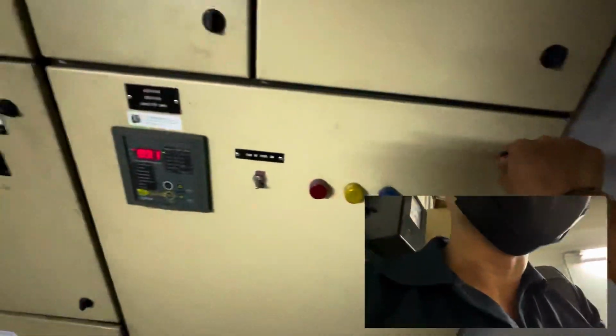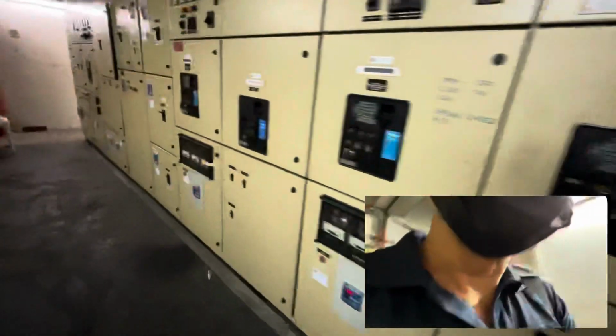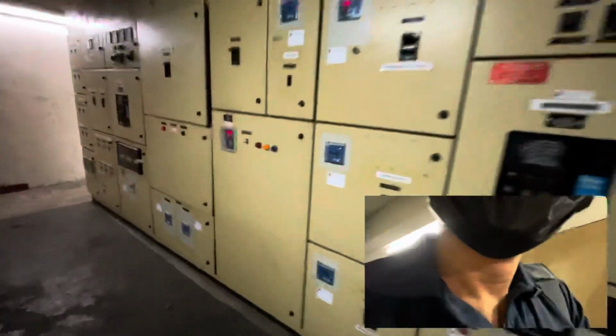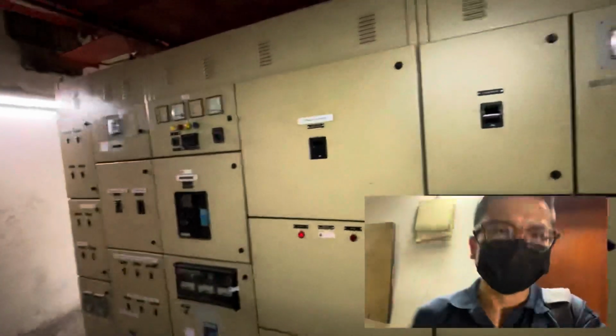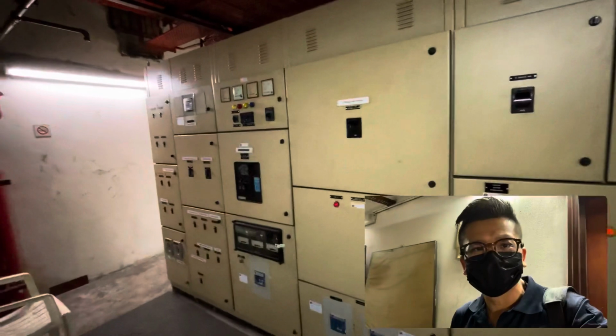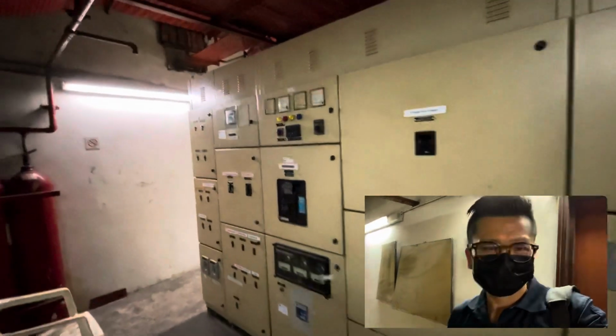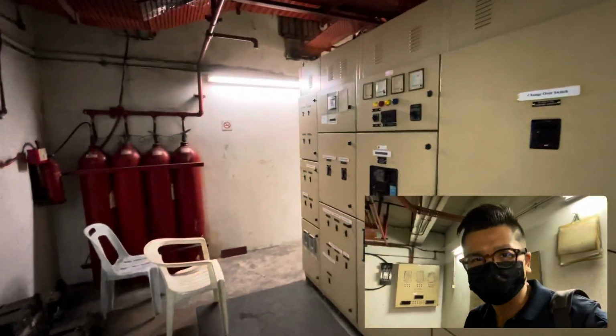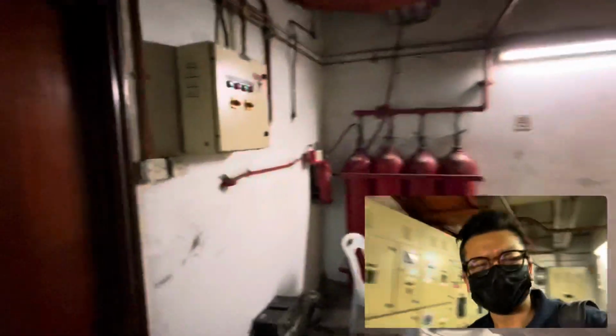Okay, step 3 faulty, step 1 faulty, step 8 faulty, step 9 faulty, step 10 faulty. Okay, fuse faulty, need to replace. We'll have to replace the cap bank first. Alright, later on we're going to test run this genset using a jump wire from the ATS panel in a remote way. But before we test run the genset, we're going to check the genset parameters first.